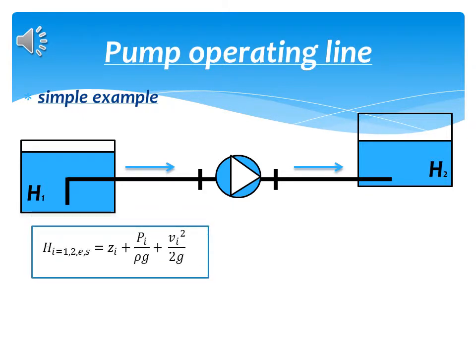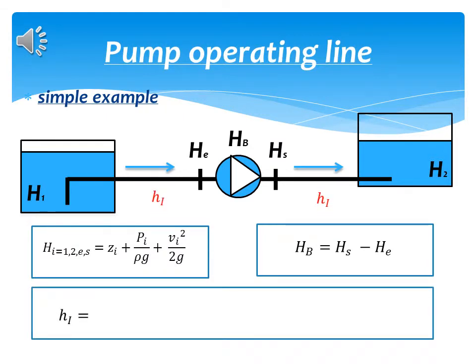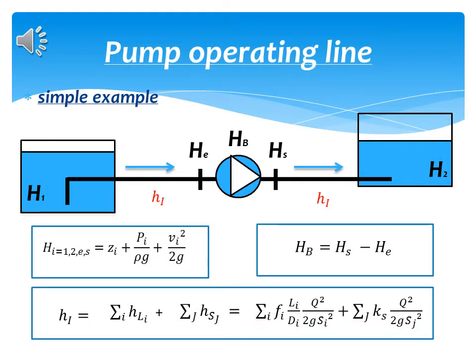In most cases, the height of the pump is usually provided by the manufacturer, but it can also be calculated as the height provided by the difference between the suction flange and the impulsion. But the fluid does not flow ideally. The installation prevents fluid transport. This resistance results in what is known as losses, which can be linear losses caused by the pipe itself, and singular losses caused by valves, changes of direction, and changes of section.